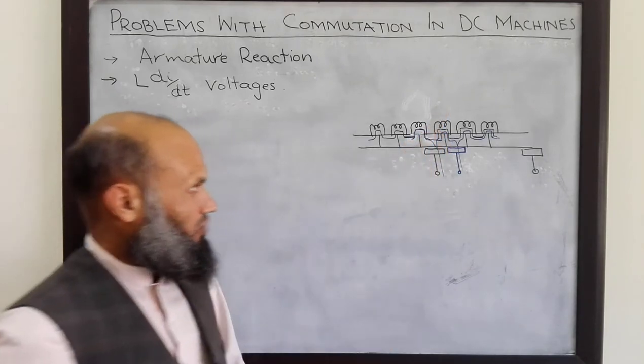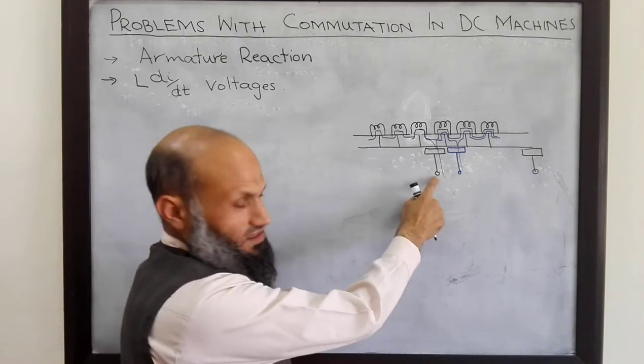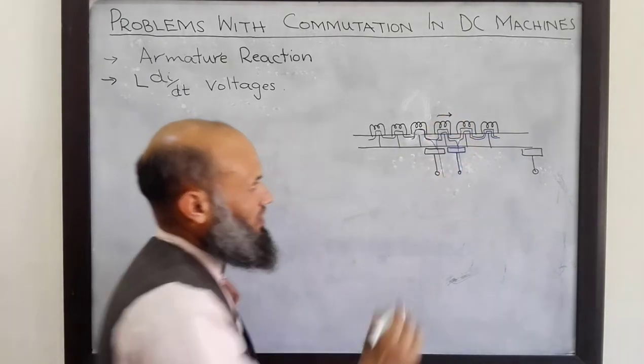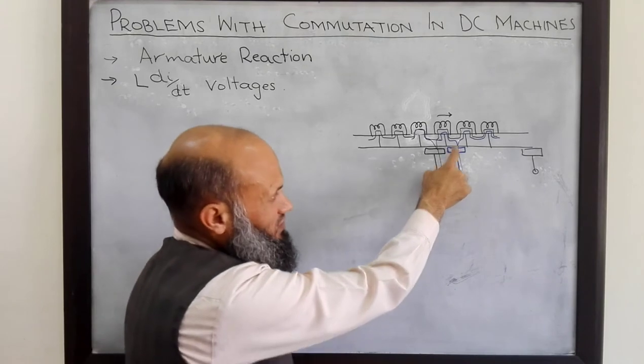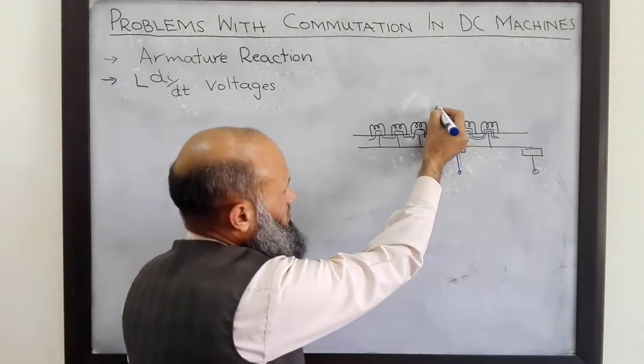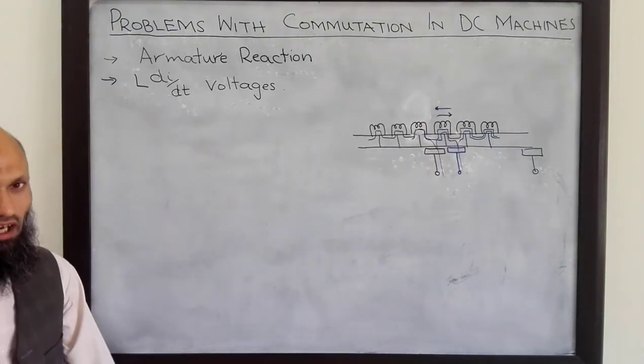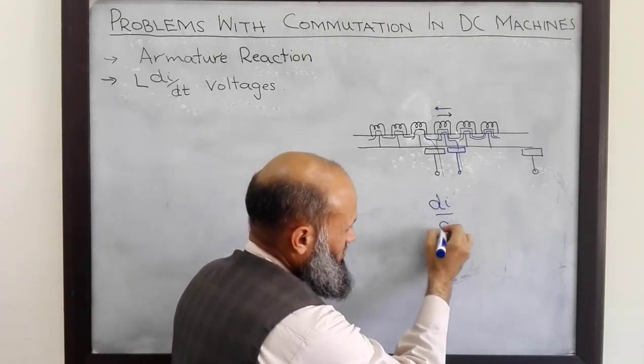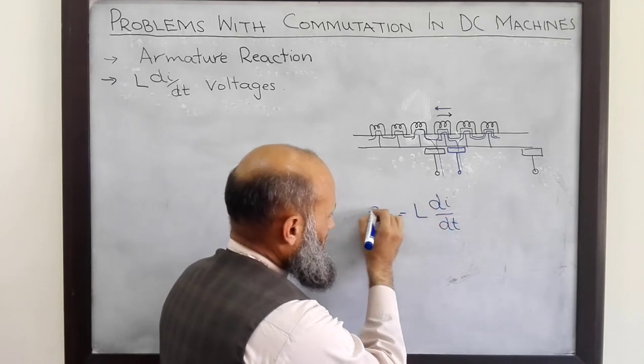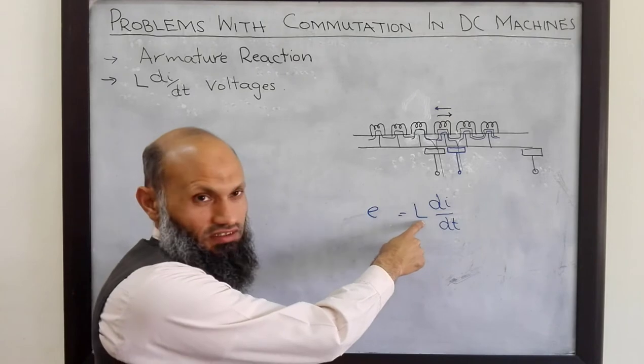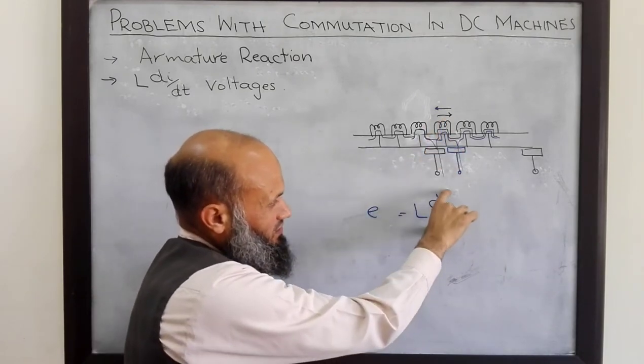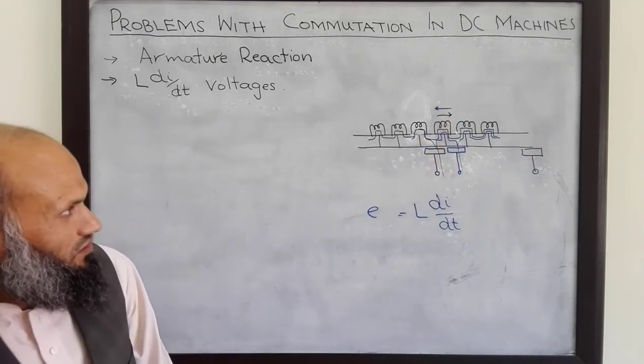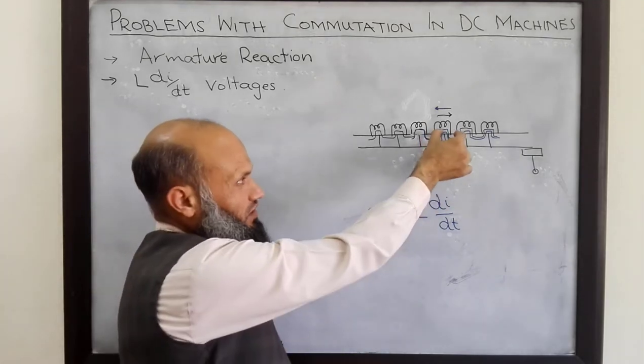Now carefully look at this coil. When the brush was in contact with this commutator segment, the direction of current in this coil was in one direction. And now, when the brush is in contact with this commutator segment, the direction of current in this coil has been reversed. We know that in an inductor, when there is a rate of change of current, there is a voltage across that inductor. And even if L is small, di/dt is quite large because the direction of current has quickly reversed, and therefore a high voltage will appear across this inductor.